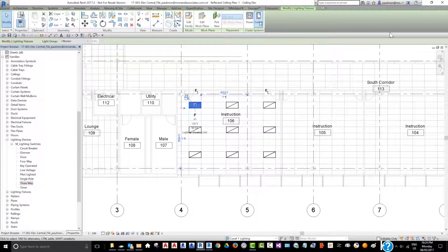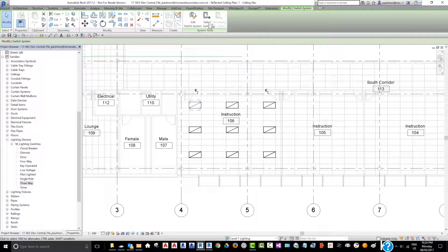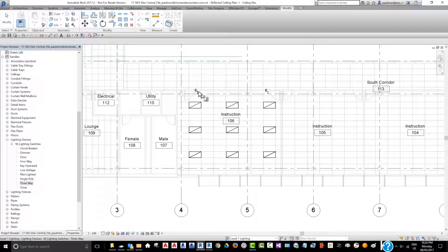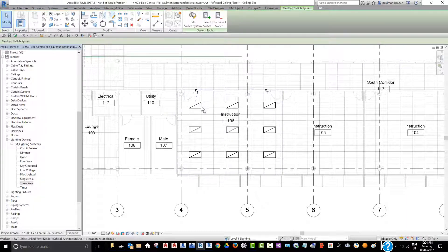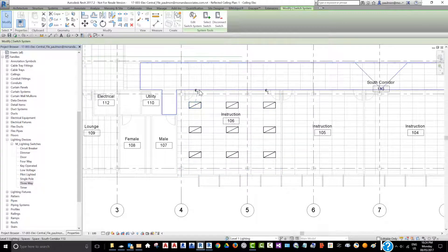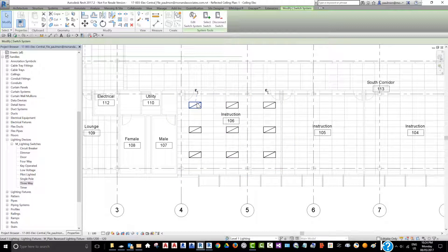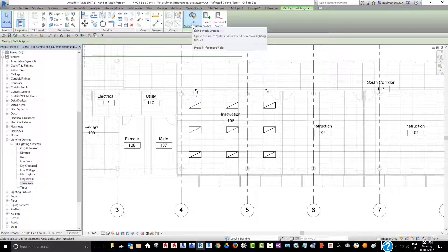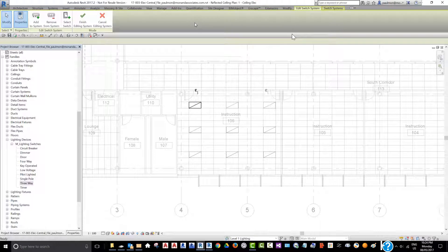We're going to click on Switch and pick the command Select Switch, and we're going to select this switch. You can see there's a dashed line associating this switch circuit with the light fixtures. Afterward, the switch system is selected, so we can go in, select Edit Switch System, and now we can click on Add to System. Make sure this is highlighted — I'm going to add the light fixtures.